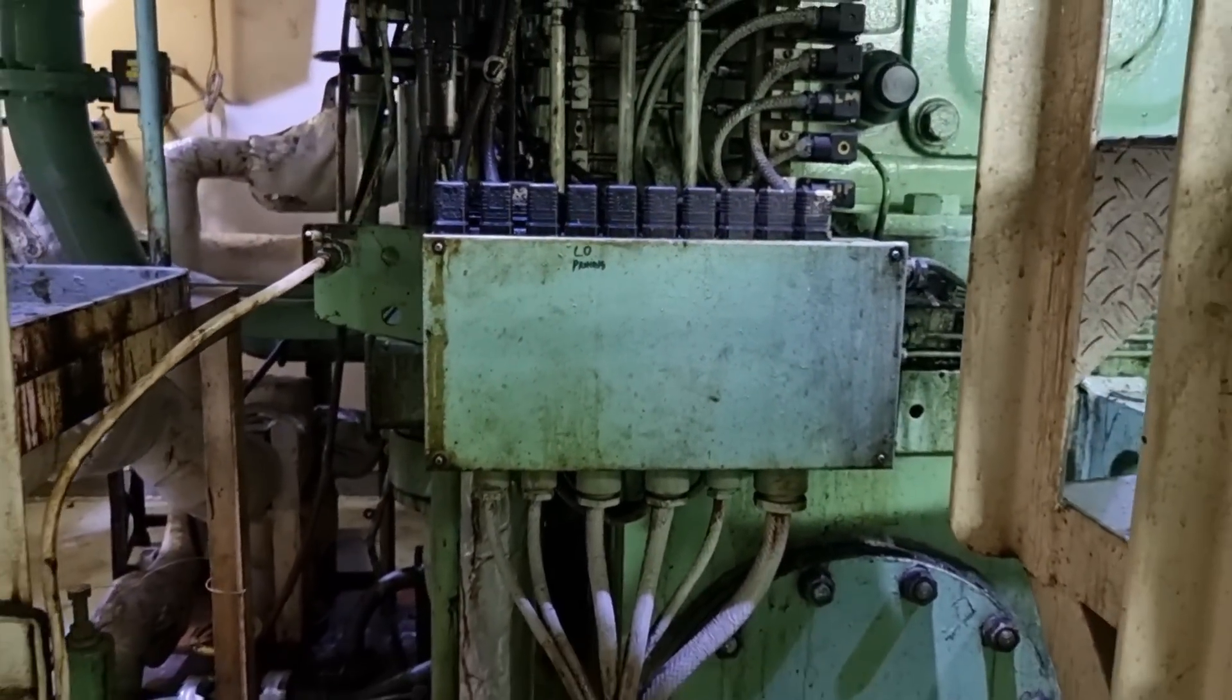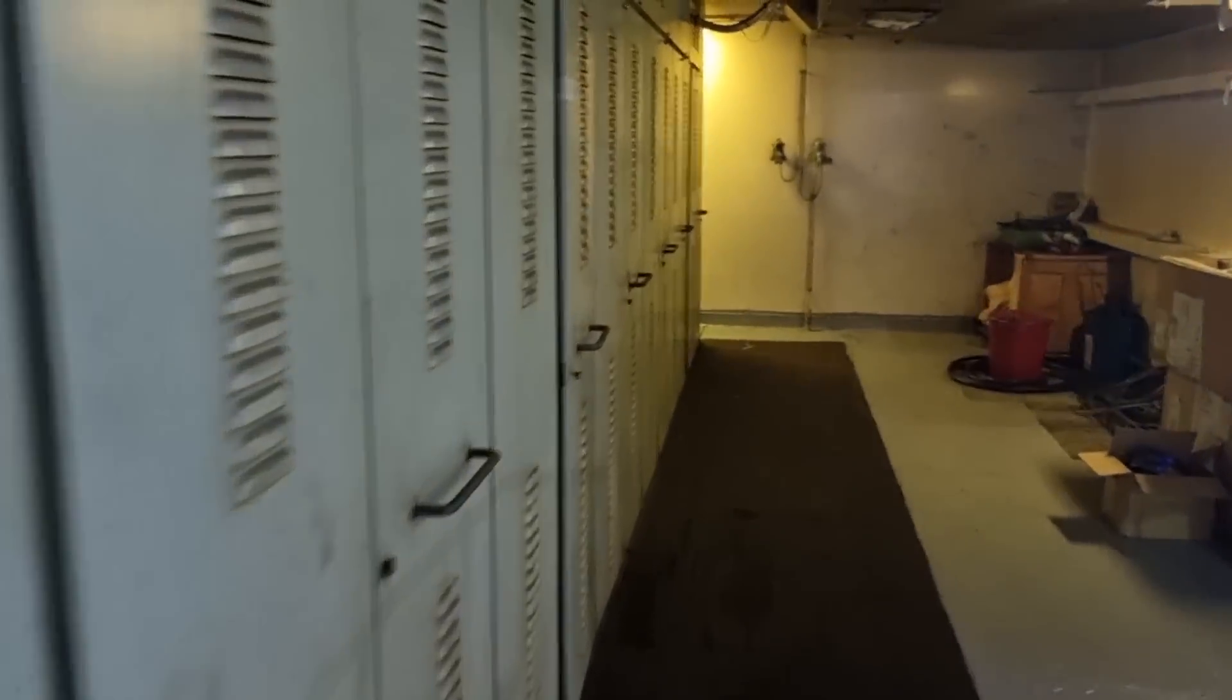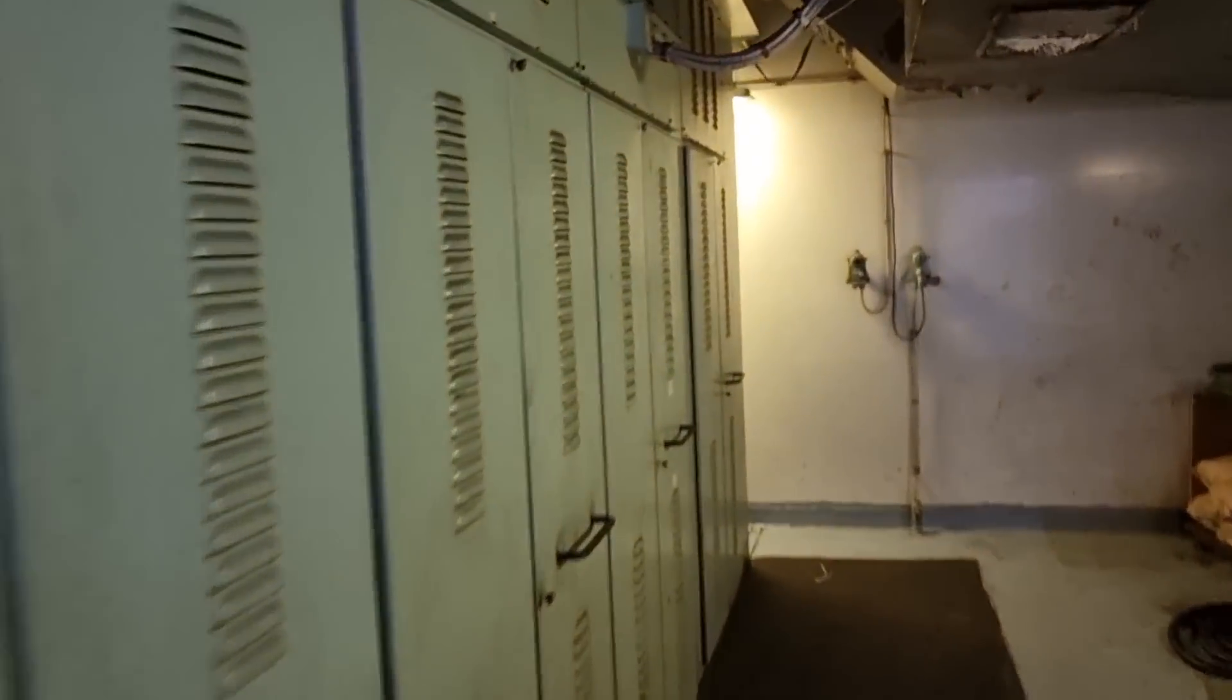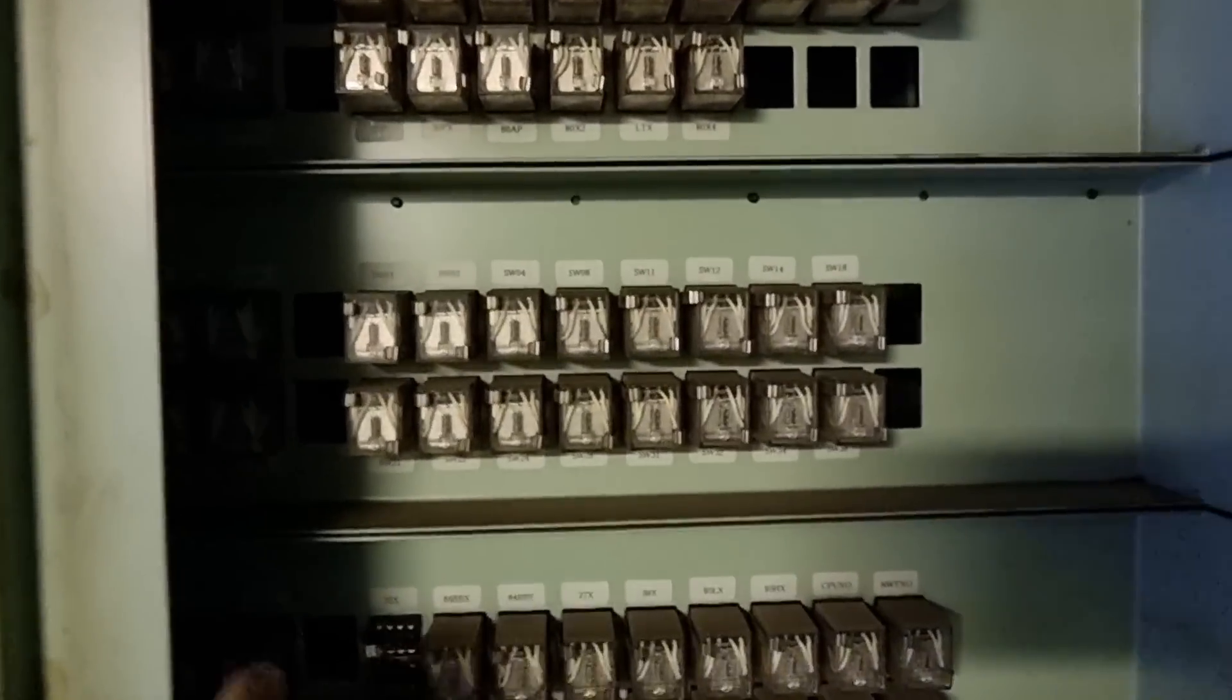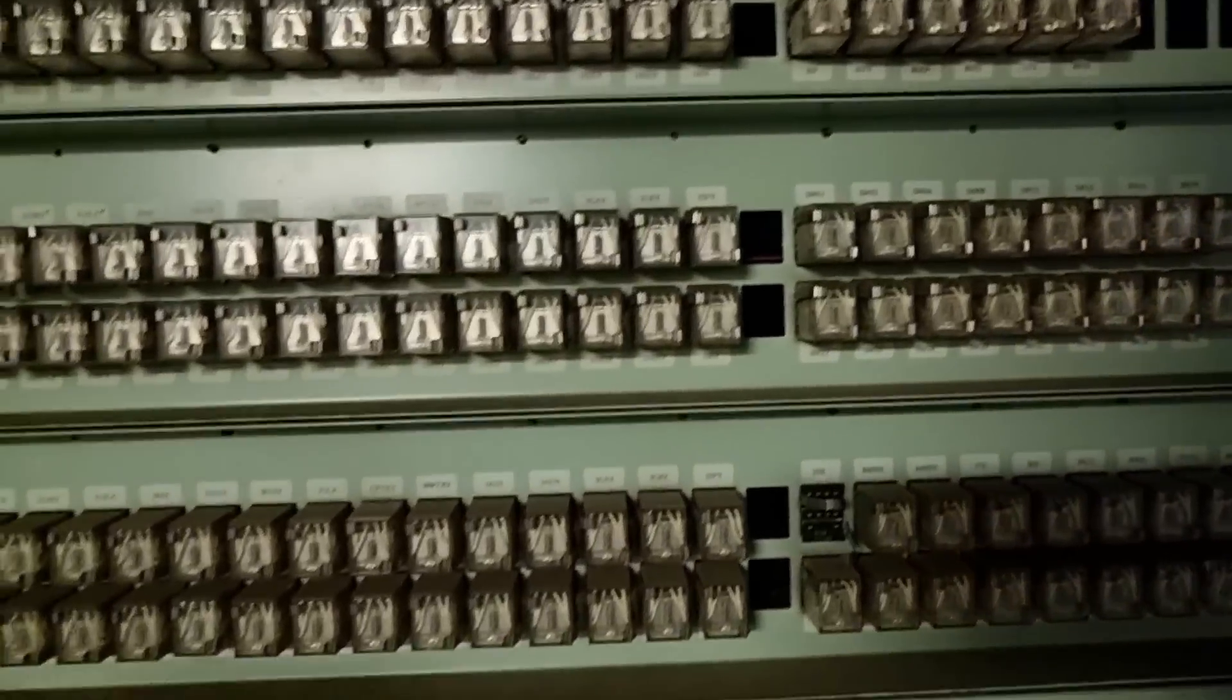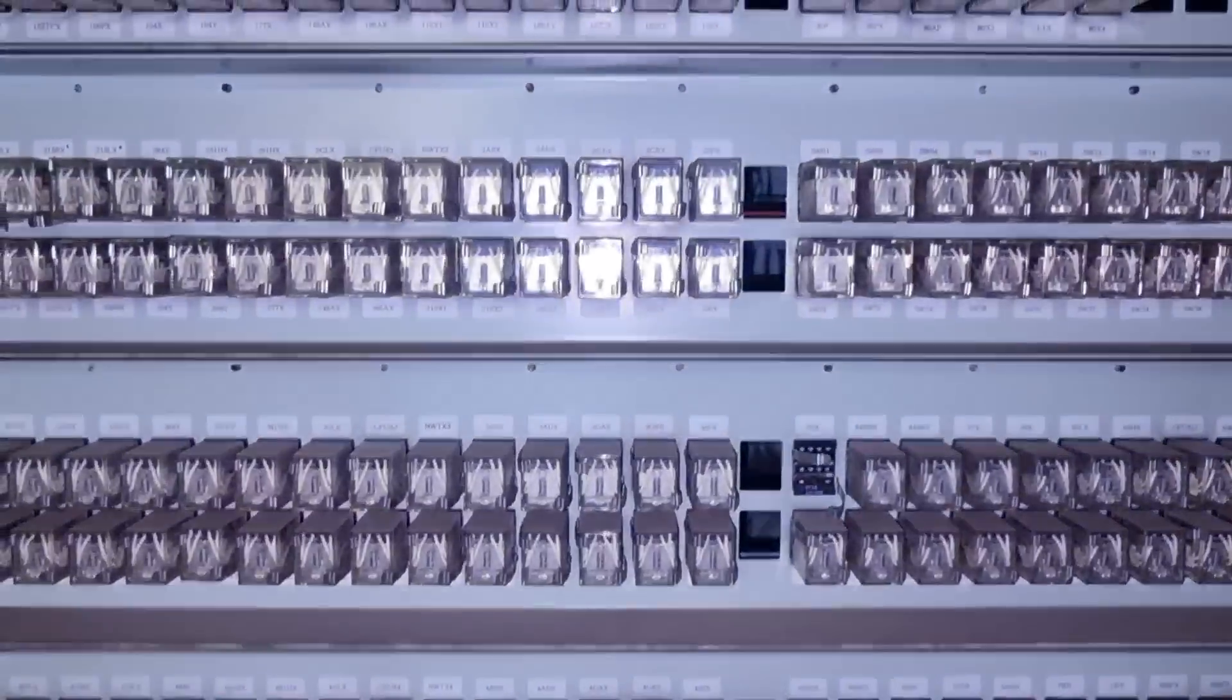So since we can't stop the generator in local operation, we will start checking the remote operation. Why is it that this generator cannot stop? So this troubleshooting will be focusing into the reading of the wiring diagram.